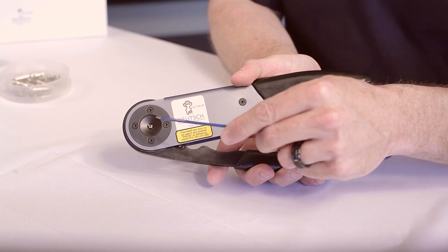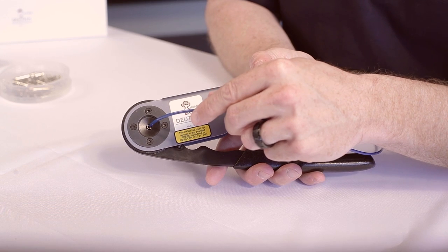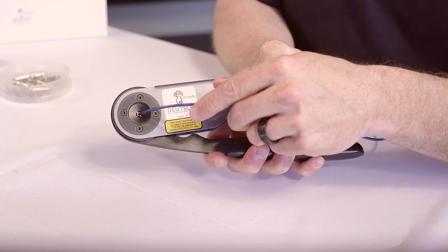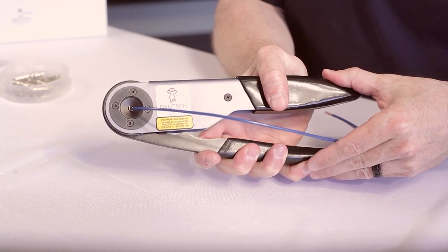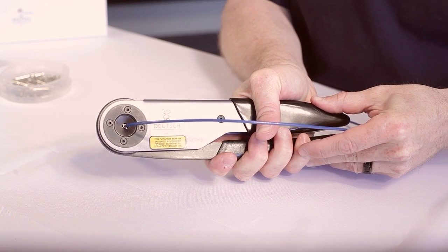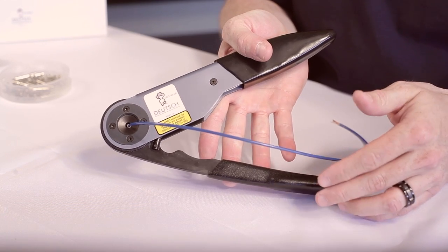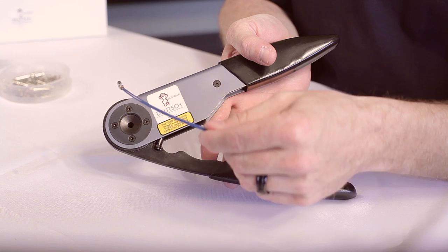Insert your correctly stripped wire into the crimp barrel until it stops and squeeze the handles together. The locking ratchet action won't release the crimping die until you fully close the handles. Once the handles have been fully closed and your crimp is completed, they will automatically release and you can remove your contact.